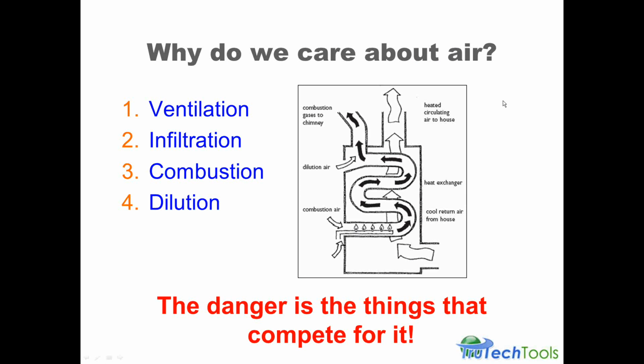So why are we talking so much about air? I thought this was combustion. Well, air comes in different forms. It basically has different labels that we give it. There's ventilation air, that is the air that we control that comes into any kind of structure. There's the infiltration air, which is the air that's uncontrolled and comes in through unknown sources into a structure. There's the combustion air, which is the right amount of air that we need to make the combustion process happen correctly.